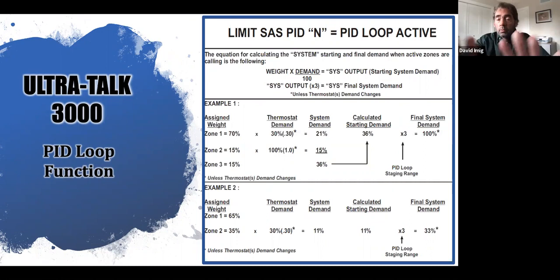So think of this whole thing as a formula. These percents that you see are not the percentage that your equipment is operating at. These percents are part of a formula that helps determine whether you stage up or stage down. So with that in mind, we look at example 1. In the first column, we've got the assigned weight. Well, zone 1 is calling, and it's a 70% weight value that we gave it.